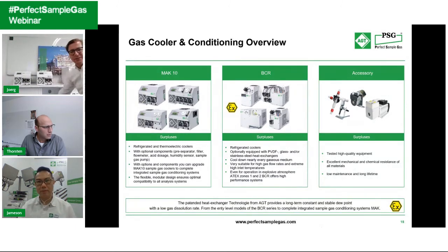At the same time, we also discussed lower detection limits, Thorsten. And maybe it's important to say that the analyzer system, the CEMS system, at least in Europe, is looked at as a complete package. That means we have the sample handling system, the probe, the heated line, the cooler, other accessories needed for probe sampling, and the analyzer - all together is measured.